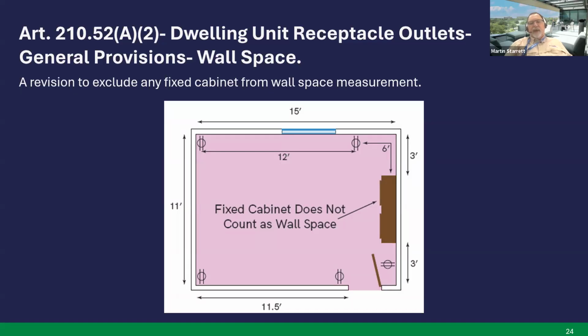210.52(A)(2), dwelling unit receptacle outlets, general provisions, wall space: a revision to exclude any fixed cabinet from wall space measurements. So you would treat a fixed cabinet pretty much like you would a door. It will not be included in your wall space measurement. It was previously, but now it's being excluded. Next slide.